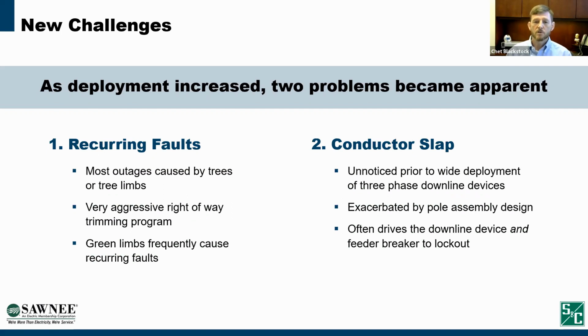We also started to notice more and more conductor slap. Now, before we had deployed a large number of devices, we didn't notice it. You really don't start to see that until you get more devices out there. And also we found that some of our pole assemblies made that problem worse, where we had a common pole assembly that we used where our center phase on a horizontal assembly would be installed on the cross arm. And then when you had two of those poles in a row, then your span, the conductors would be parallel all the way through the span. So you had no vertical separation, even though you had adequate horizontal separation. So as the fault passed through those two conductors, that swinging motion would cause them to slap mid-span. So sometimes that would cause additional blinking upline, but sometimes it would drive the upline device all the way to lockout. Next slide.